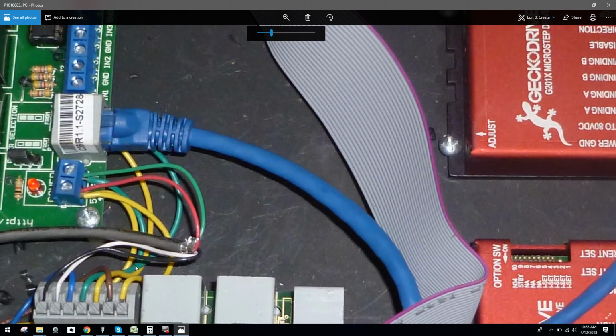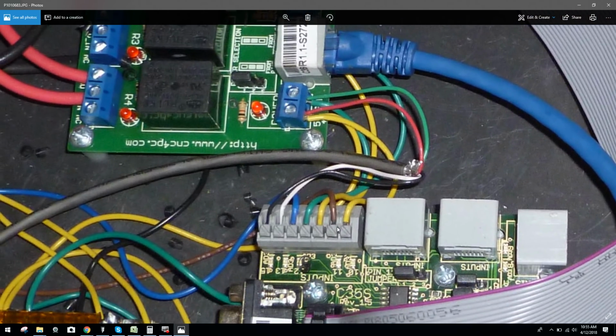Matter of fact, as we zoom in here, we can keep going. Look at this. We see more bare conductors sticking out of this quick connect terminal block. Once again, when you guys insert any conductors inside a terminal block, you should see absolutely no conductor present. It should be nothing but casing. This way you're assured that you're getting full conductivity whenever that terminal block is fastened.